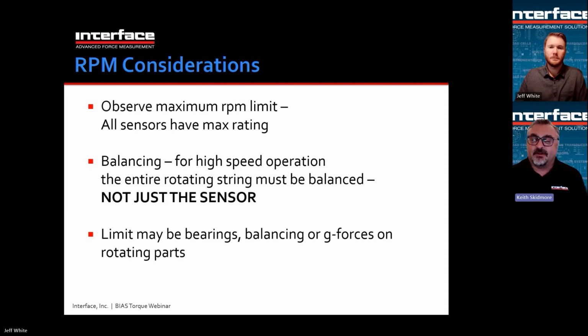Balancing. The higher something spins, the more important it is for the system to be balanced. The sensors are typically inherently pretty well balanced. Couplings are reasonably well balanced, again, because they're symmetrical. But it's not just the sensor, just the couplings. The entire rotating assembly needs to be in balance. And a lot of times that would include balancing the entire rotating assembly as an assembly, not individual pieces. So it should be considered.